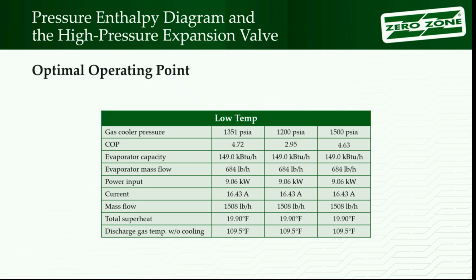Where do you see a difference? Your COP. Nothing. Just COP is the only thing that's changed. Right, and that's for the whole system. Because really, when you think about those pressure-enthalpy diagrams, that low side's kind of all by itself down there. Those systems, it's getting liquid out of the flash tank.